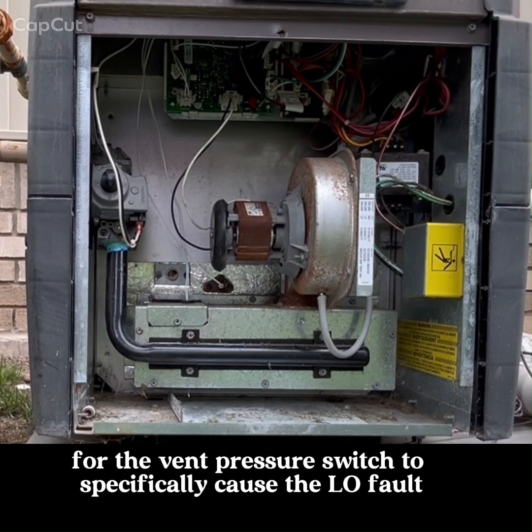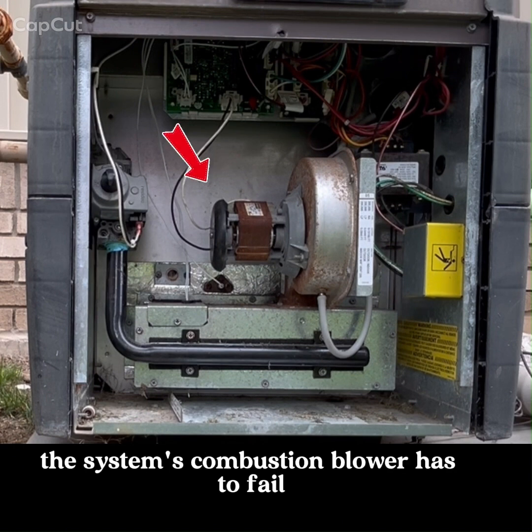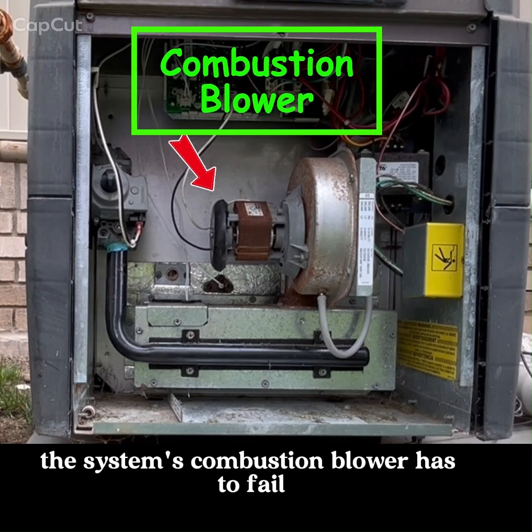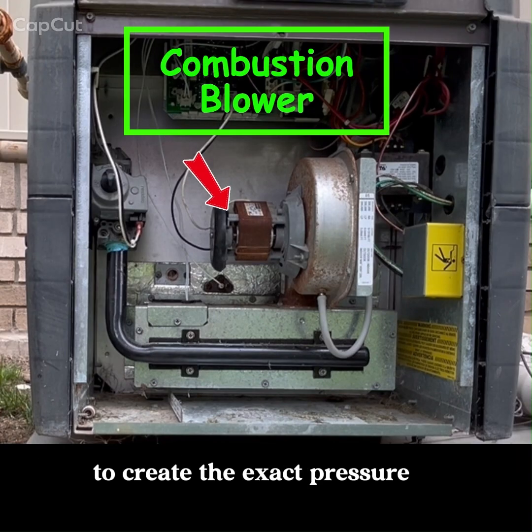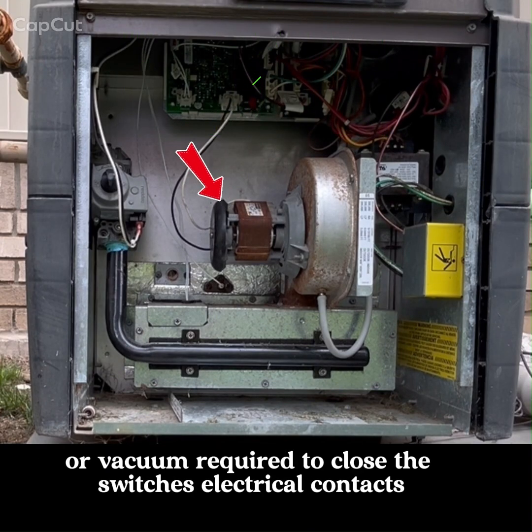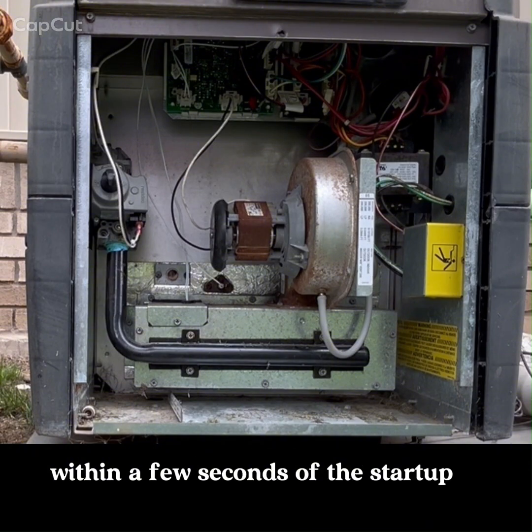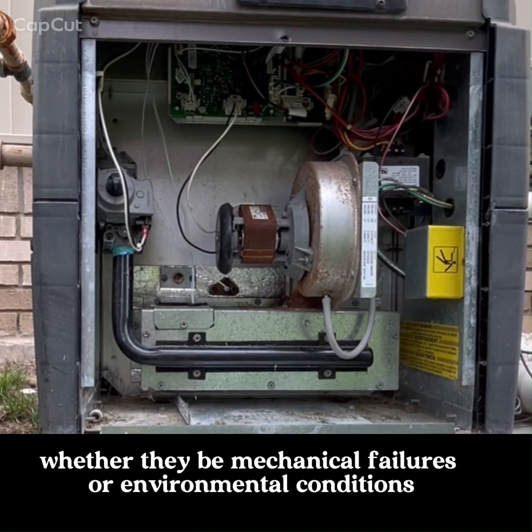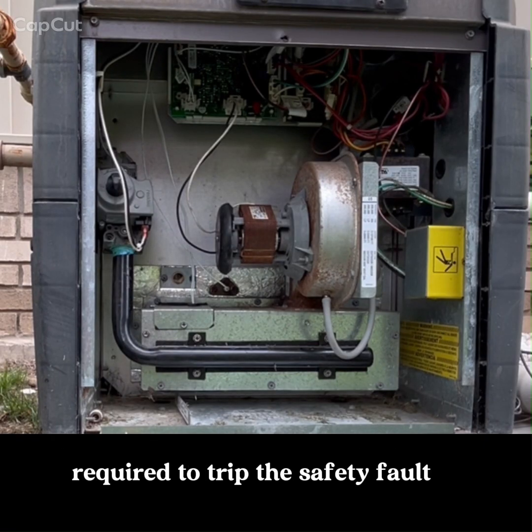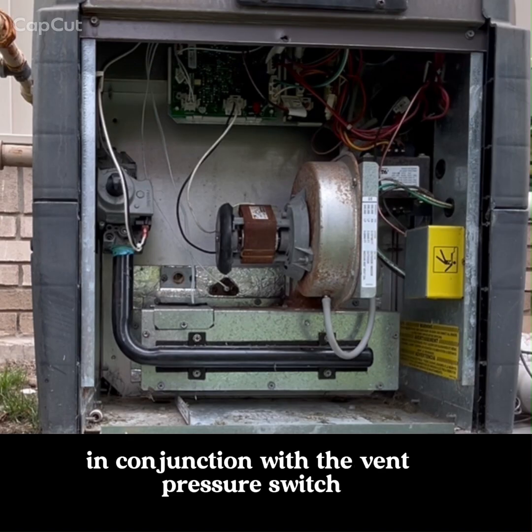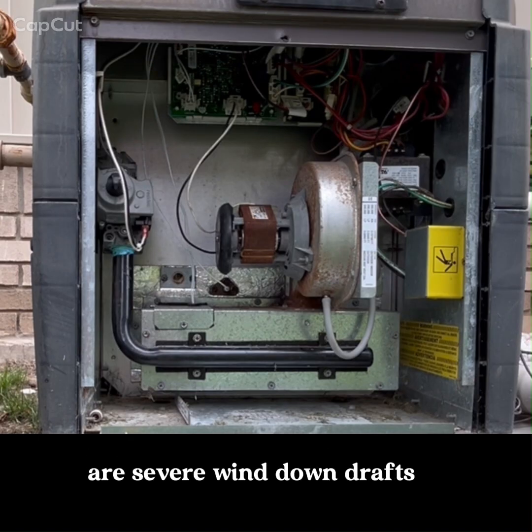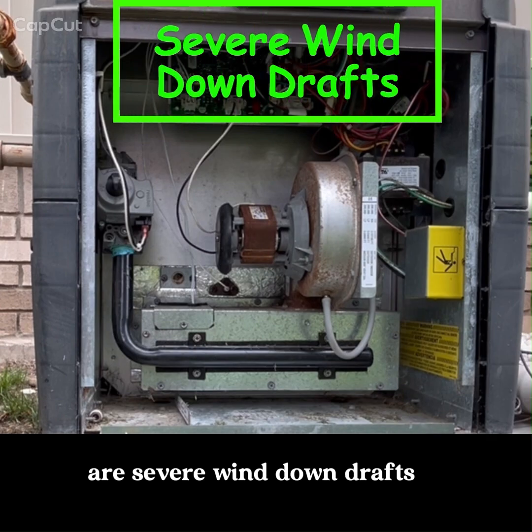For the vent pressure switch to specifically cause the LO fault, the system's combustion blower has to fail to create the exact pressure or vacuum required to close the switch's electrical contacts within a few seconds of the startup. The specific events, whether they be mechanical failures or environmental conditions, required to trip the safety fault in conjunction with the vent pressure switch are severe wind downdrafts.